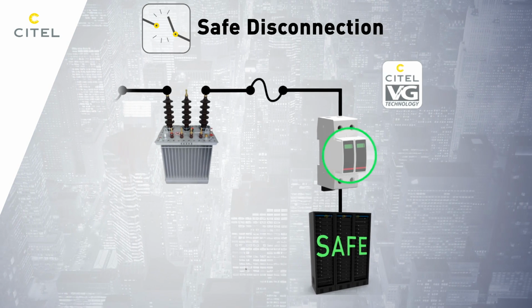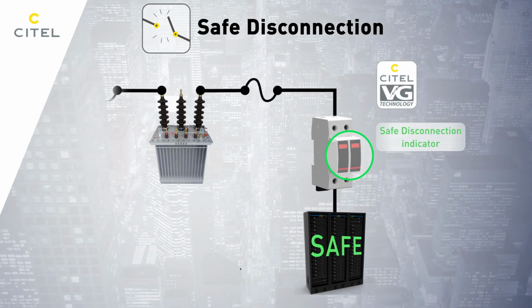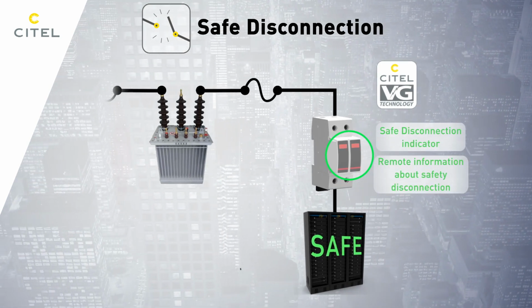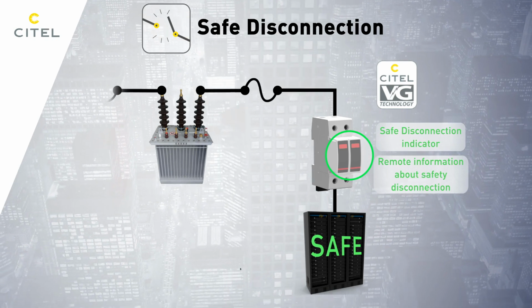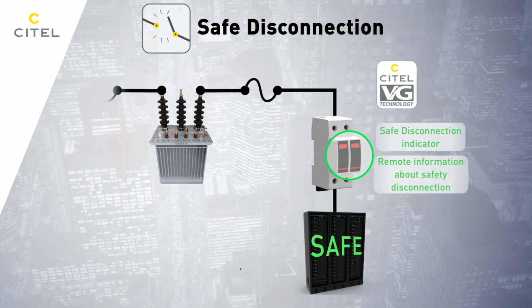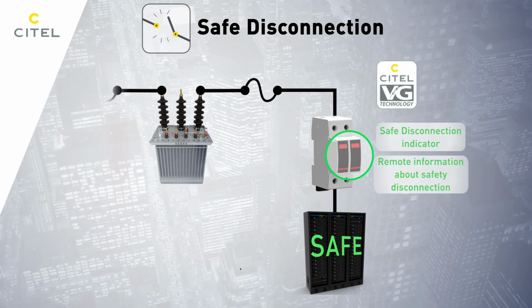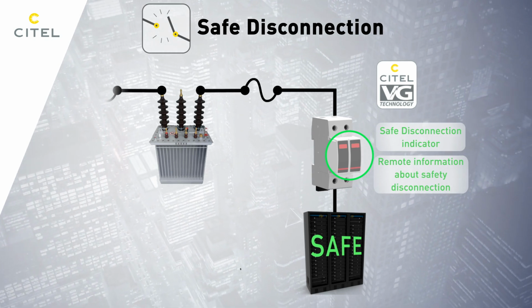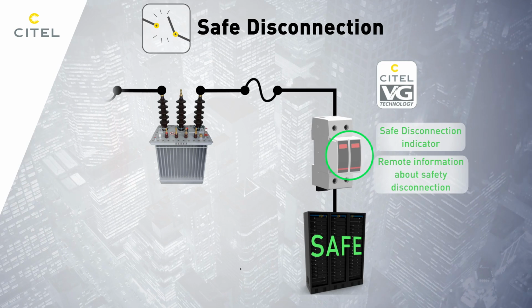Thanks to the gas-filled spark gap (GSG) disconnection mechanism, the current is interrupted as long as the MOV still retains a small residual resistance. This enables the thermal disconnection to function without load current, significantly reducing the risk of an unwanted arc and potential fire.